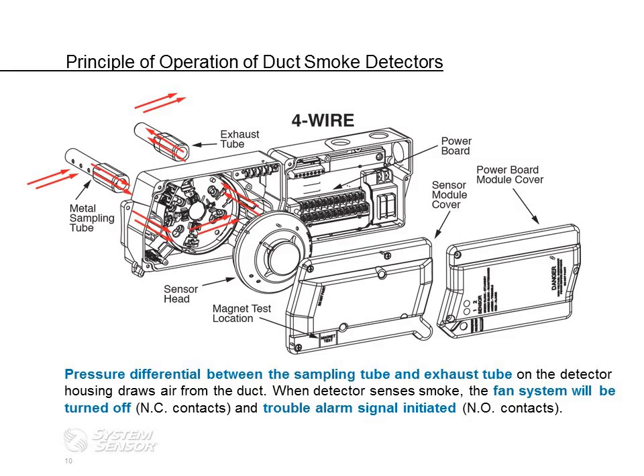So how do they actually work? What is the principle of operation? Basically, a duct smoke detector is a smoke detector in a housing that uses pressure differential between the sampling tube and the exhaust tube to draw an air sample out of the ductwork and route it through the chamber of the smoke detector to check for smoke. When the detector senses smoke, it will go into alarm. The relays will change state on the control board side, and that will in turn shut down the fan of the air handler, or cause an alarm at a fire panel, activate a trouble alarm, or a remote test accessory.